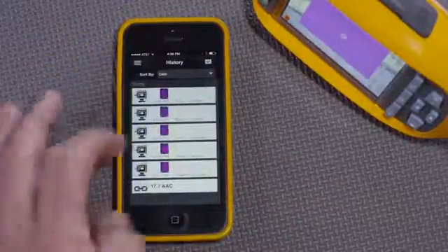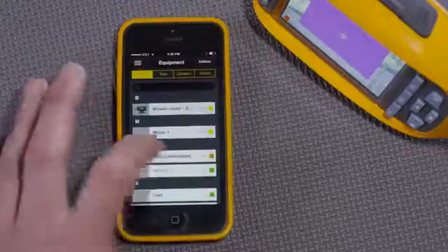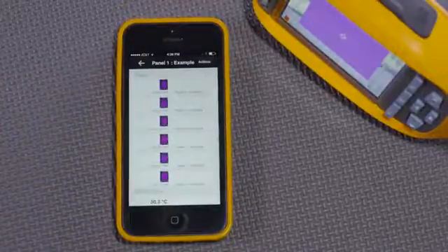To check, I'll look at equipment, panel 1, and see that the latest thermal image is right there at the top. I've simulated the circuit getting hotter. We can see that the thermal imager shows that this circuit is hotter.